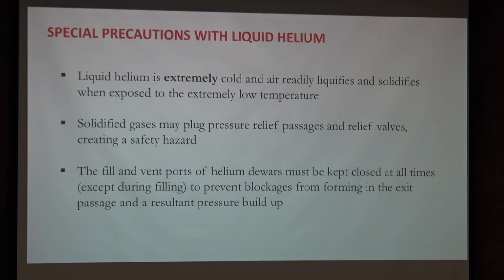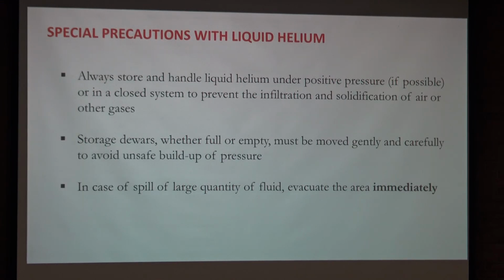The fill and vent ports of the helium dewar should be closed all the time, except when you're actively transferring helium. When transporting your dewar, you want to keep the escape port open. For the same reason, you always want to store and handle the helium dewars at slightly positive pressures to avoid stuff being sucked into your dewar and forming some danger due to blockages.